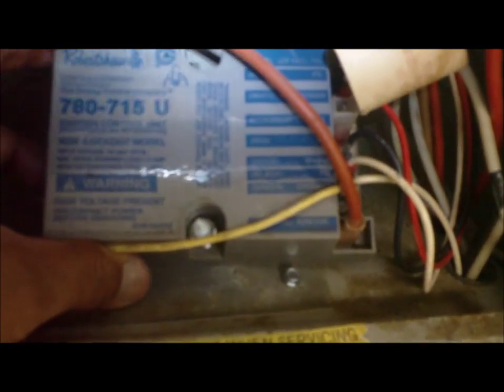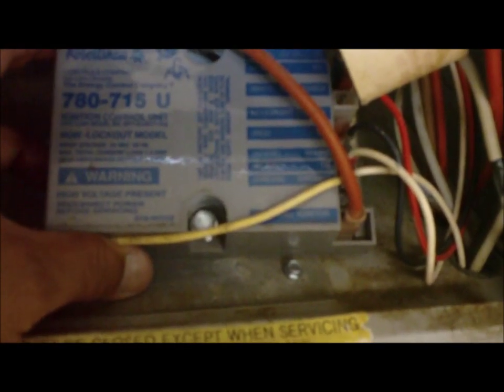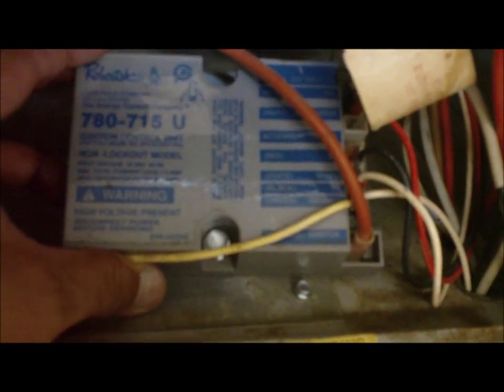And also there's your limit switch, and this is your gas valve and the gas burners, and right in there, hopefully I can get the light in there. Okay, that's your igniter, and this is your ignition control unit, which is powered by 24 volts. This unit has your power going into the gas valve, 24 volts. Also, this one right here has your igniter that connects right here.